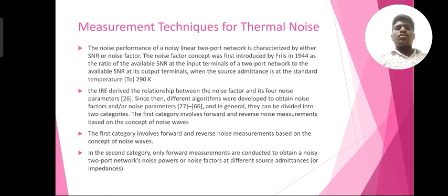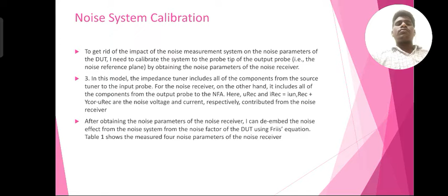Noise system calibration. To get rid of the impact of the noise measurement system on the noise parameters of the DUT, I need to calibrate the system to the probe tips of the output probe, that is the noise reference plane, by obtaining the noise parameters of the noise receiver. In this model, the tuner includes all of the components from the source tuner to the input probe. The noise receiver, on the other hand, includes all of the components from the output probe to the NFA. Here, U_REC and I_REC are the noise voltage and current respectively contributed from the noise receiver. After obtaining the noise parameters of the noise receiver, I can de-embed the noise effect of the noise system from the noise factor of the DUT using Friis's equation.